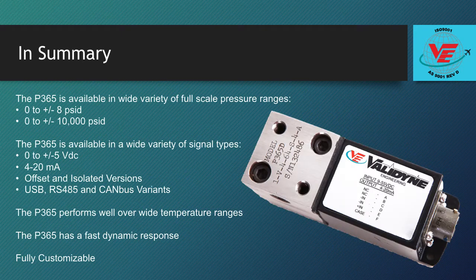In summary, the P365 is a compact, robust pressure transducer that is available in a wide variety of pressure ranges, from units with full-scale pressure of just plus or minus 8 psi differential, up to high pressure sensors for plus or minus 10,000 psid or 10,000 psig gauge. The P365 is available with a wide variety of standard signal types, 0 to 5 volts DC, 4 to 20 mA, as well as the offset calibrations and isolated output types. In addition, there are new variants of the P365 that include USB and RS-485 digital interfaces. The P365 is digitally corrected for high performance over wide operating temperature ranges, and the P365 has a very fast response, making it suitable for dynamic pressure measurements.